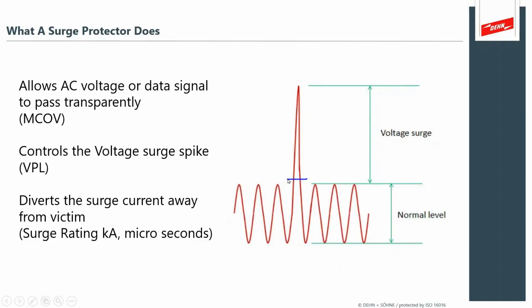It sits there transparently and allows your power and your data to operate in a normal, clean, blue sky day. So that's the day your electrical system gets installed. It's brand spanking new and it has no deterioration. Nothing's ever gone wrong. But over time, you get lots and lots of lightning, and those voltage surges induce stresses electrically into your systems. So what we're doing is we're controlling that voltage to some predetermined level, and everything above it, it chops off or diverts.